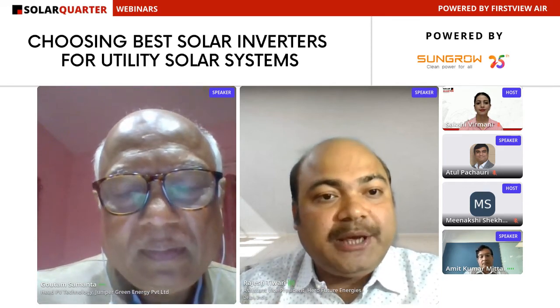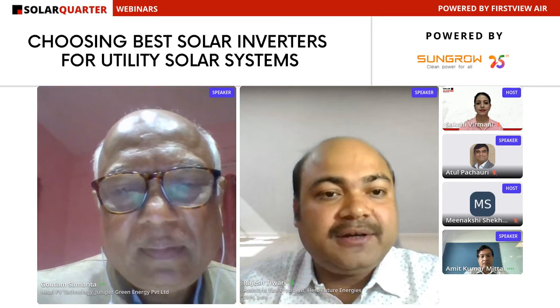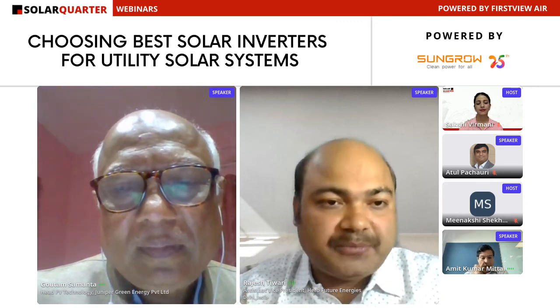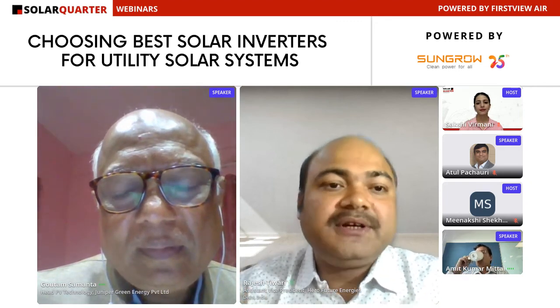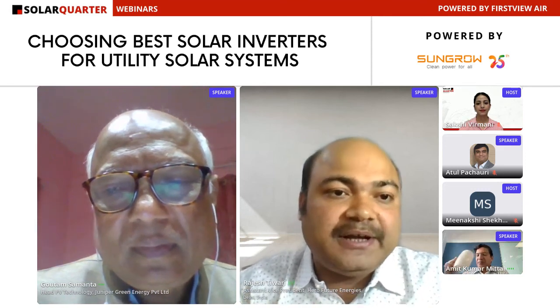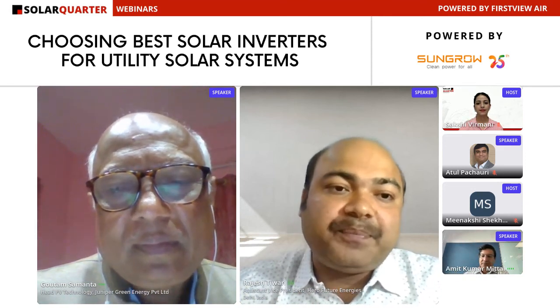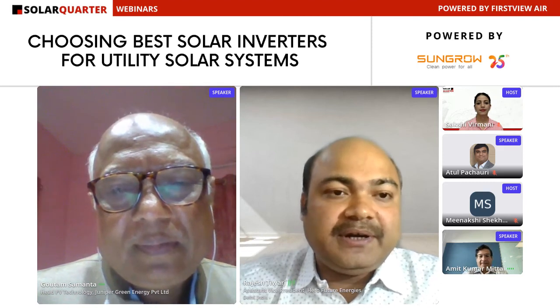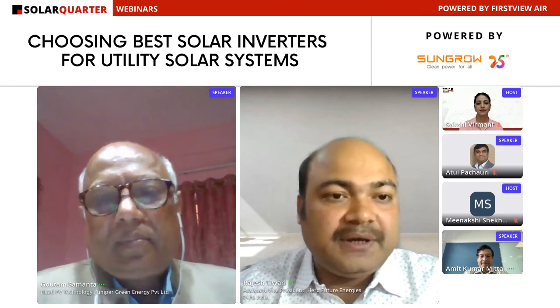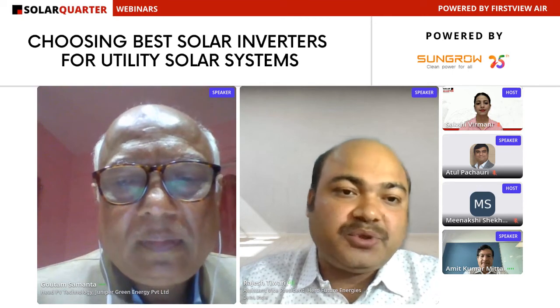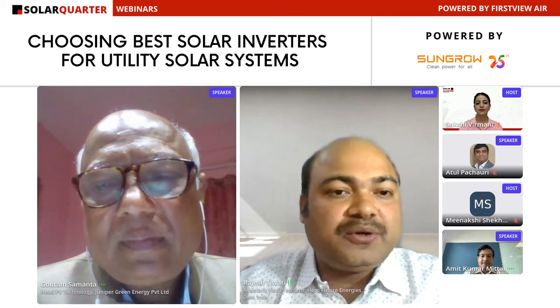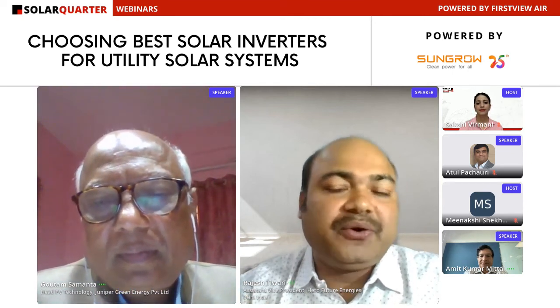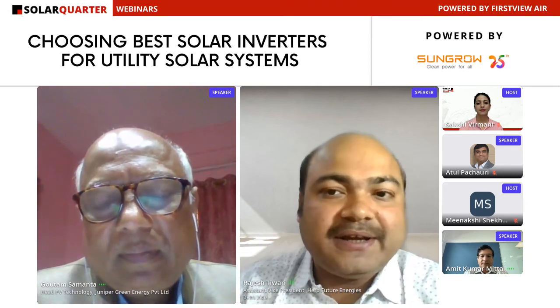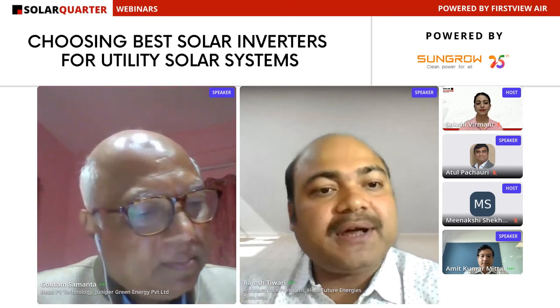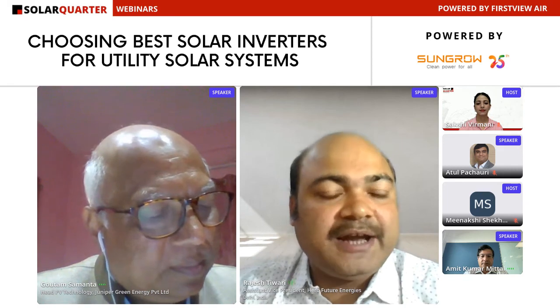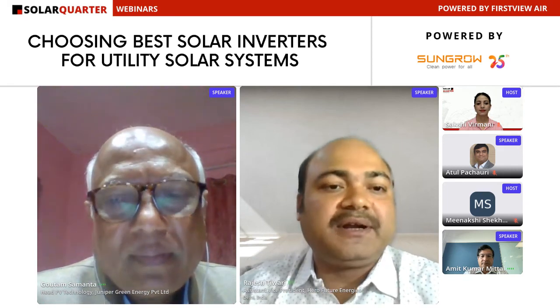So they should also keep some memory or recording, because at the inverter level, of course there is a cost, but they should record data. At the PQ meter level even DR recording is there, and at the switchyard level there is recording too - both should get synchronized. So basically central inverter can be better in response time, but in other aspects like mismatch and MPPT, string inverter is better as well.